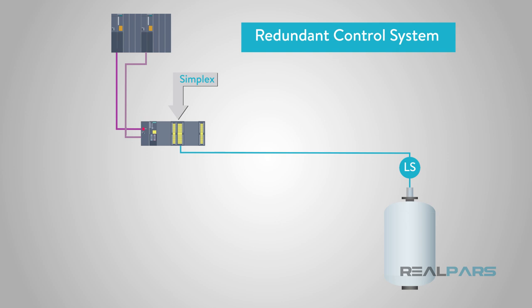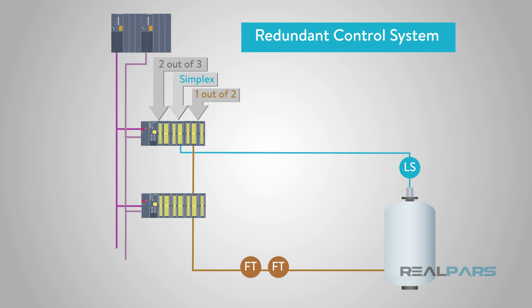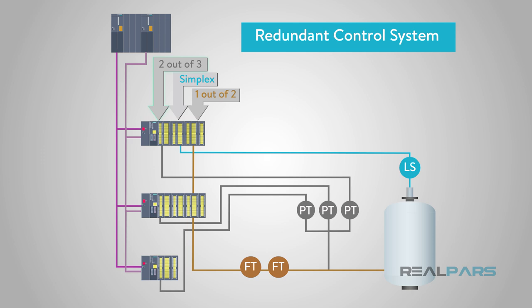Another way to reduce risk is to add redundancy. Redundancy adds cost, but generally will increase the reliability of the system and reduce risk. A 1-out-of-2 system will provide a greater level of safety response than a simplex system. A 2-out-of-3 fault-tolerant system can provide a greater level of safety response than a 1-out-of-2 system. While the 2-out-of-3 system may be more reliable, it may be installed at a much higher cost than a 1-out-of-2 system.